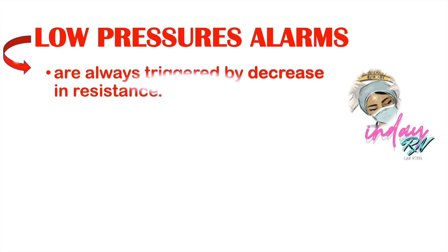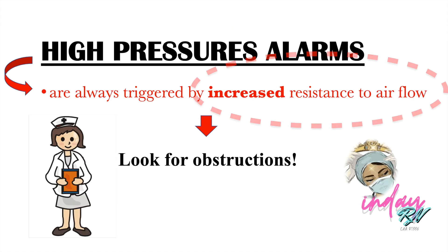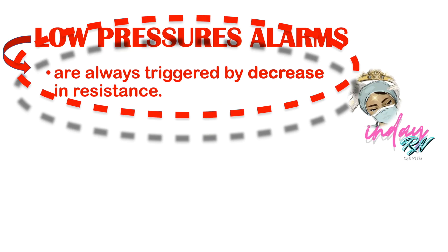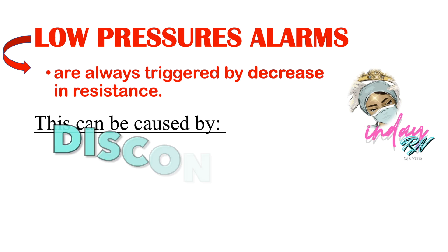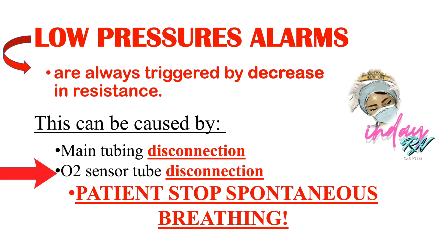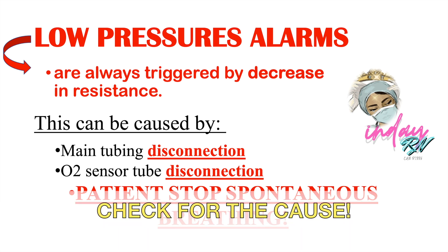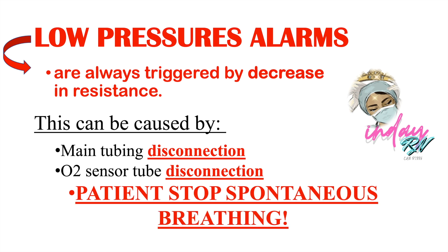Now let's discuss low pressure alarms. These are triggered by a decrease in resistance to airflow — the opposite of high pressure alarms. Low pressure alarms can be caused by disconnection: either main tubing disconnection or the O2 sensor tube disconnection. Always check for the cause. If there is a low pressure alarm, the patient may have stopped spontaneous breathing.